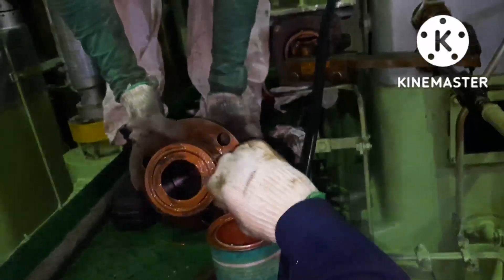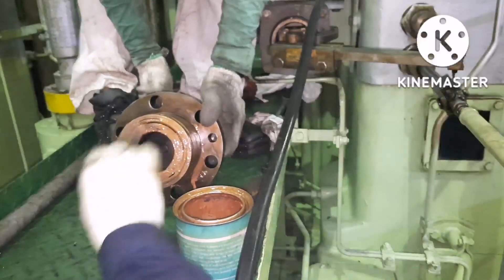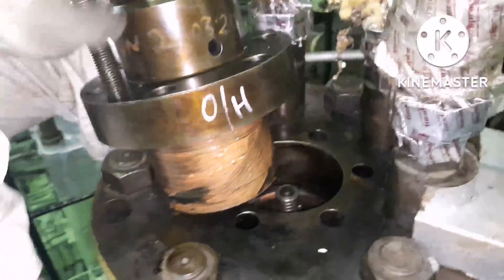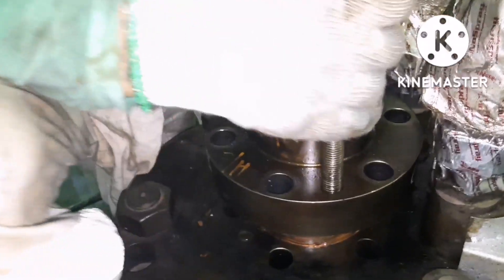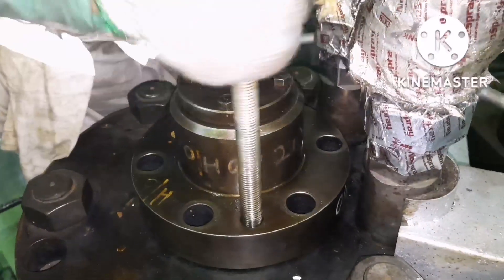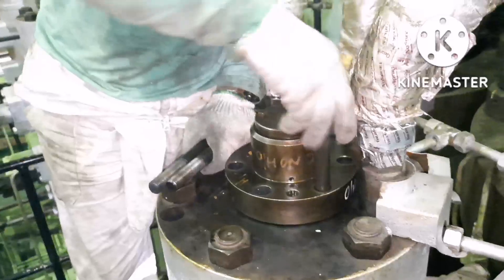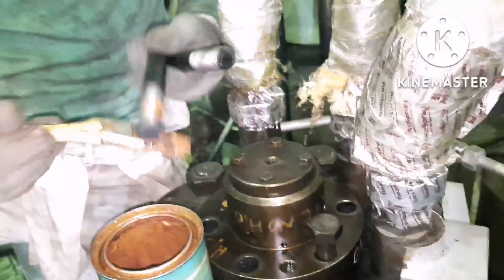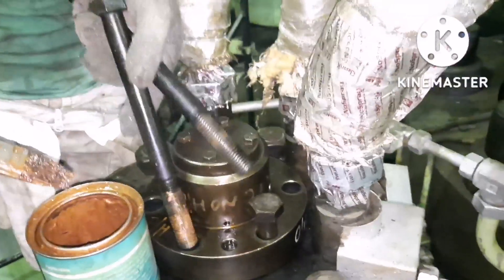Ensure the o-ring is renewed and is in place during the entire job. Just match the bolt holes, insert it, and we are done. Next, fix the bolts and tighten them. For the bolts, again apply anti-seize like Molykote or Copaslip, and fix the bolts. Tighten the bolts as per the tightening procedure given in the manual — usually you have to tighten diagonally. That's the general rule.